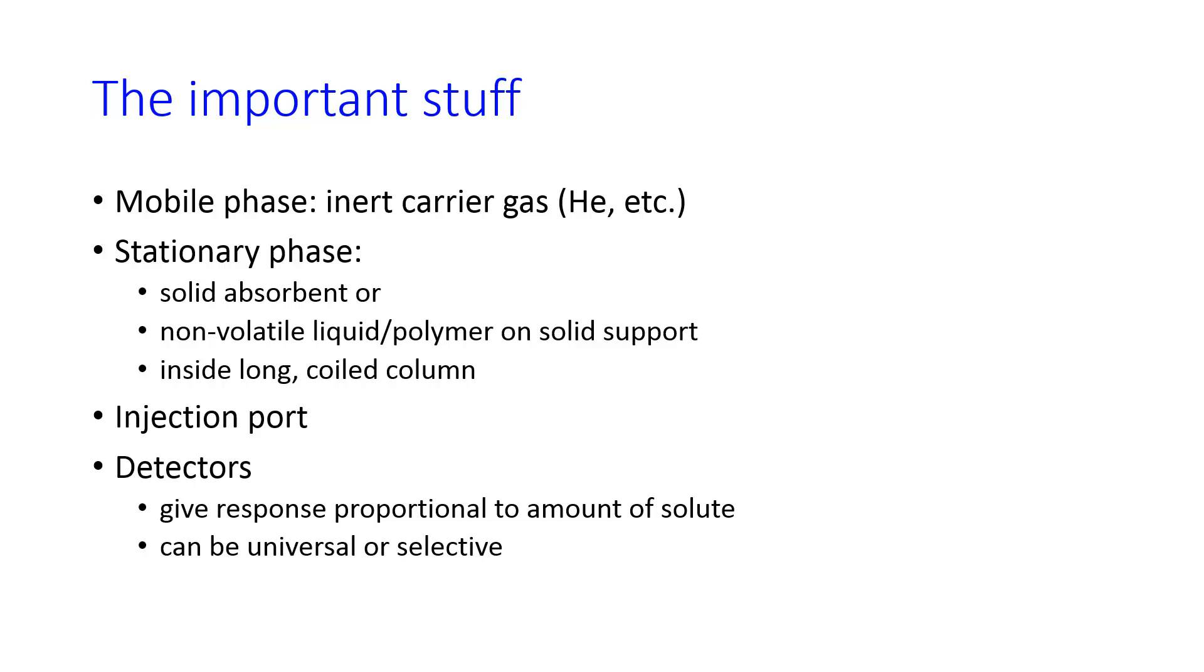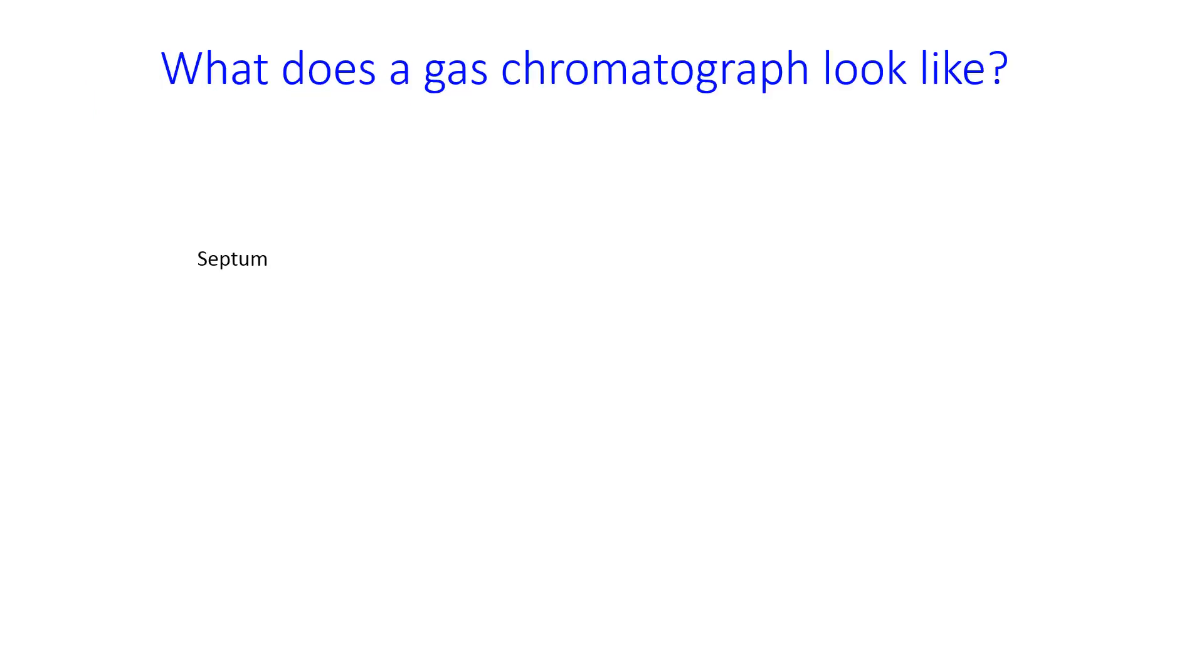First thing we'll talk about is what does a GC instrument look like. The first thing is that there is an injector oven. This injector oven is where the carrier gas comes into the instrument and is mixed with the analyte, and it carries the analyte through the instrument. The injector oven is heated because a gas chromatograph separates analytes based on their boiling point, and so the first thing that has to happen is that they have to be in the gas phase.